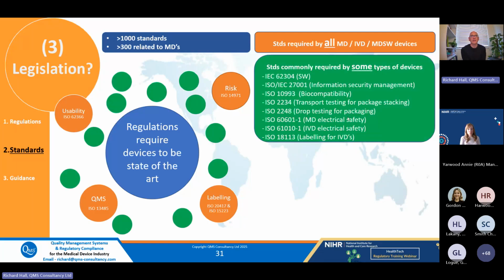And then there are ISO standards that apply to a lot of medical devices. So if your product has got software in, then the IEC 62304 software standard is extremely important. If your electronic device connects to the internet, then the ISO IEC 27001 for cybersecurity is important. If your medical device touches the patient, then 10993 for biocompatibility is important, etc. You'll see that there is one for electrical safety of medical devices, 60601-1.